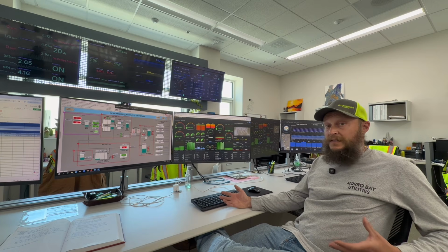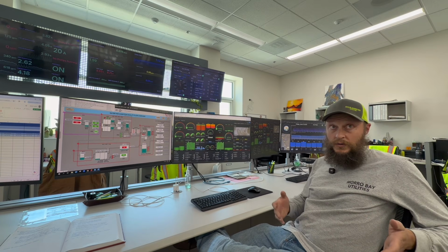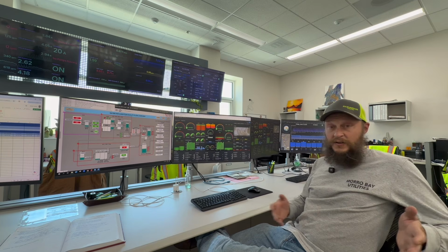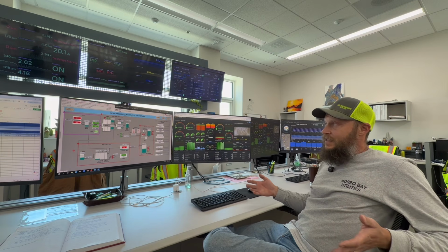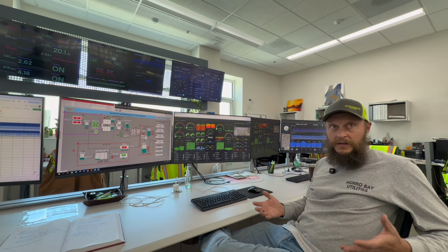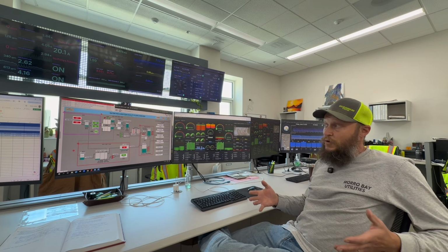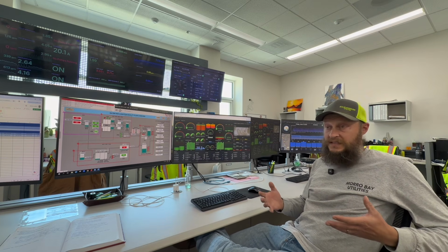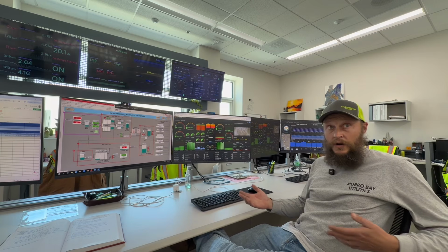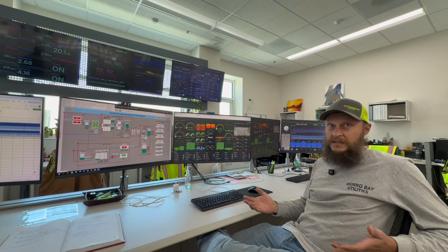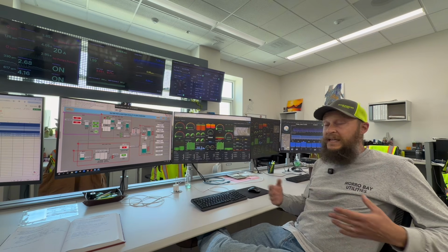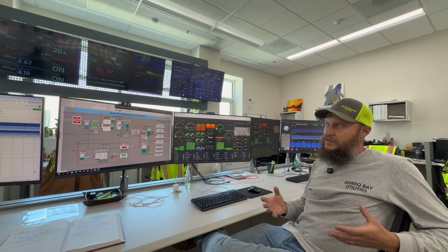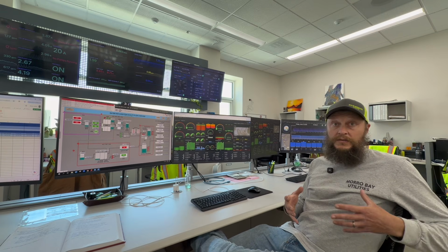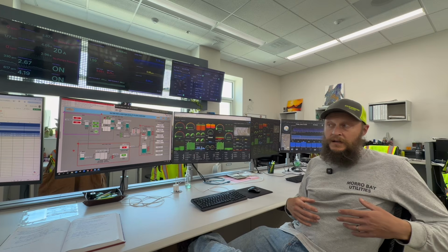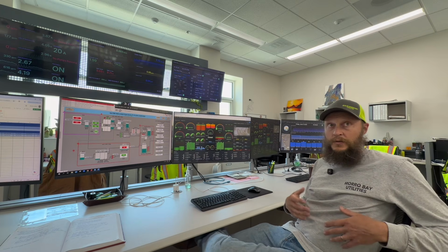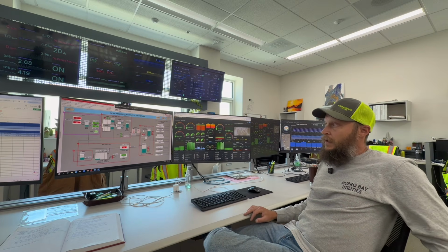And of course, if you break down the acronym, Supervisory, Control, and Data Acquisition, it's on our tests, right? Yep. Supervisory means I can see what's going on in the process. Control means I can control how the process is going directly, turning pumps on or off, or maybe just controlling set points. And data acquisition is all of the sensors and run signals happening throughout the facility being recorded and put into a historian so we can track what's going on over time.